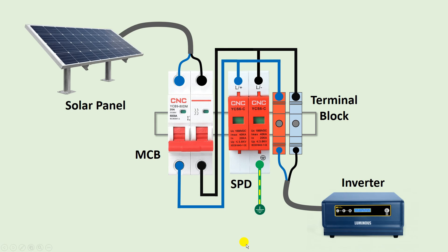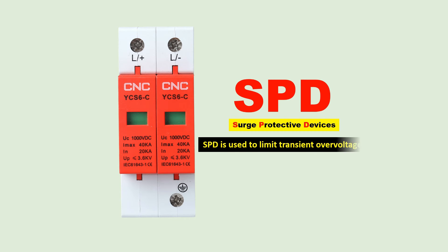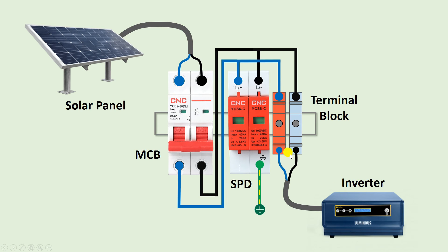Now let us understand why we should use a DC DB. As you know, sometimes suddenly voltage goes high in our homes. If voltage increases rapidly, electrical devices can become faulty. If you want to protect them, you have to use an SPD. In simple words, if the voltage suddenly increases too much, the SPD reduces it — it provides only the voltage required for the inverter. This is why the power supply from the solar panel is connected first with the MCB and then with the SPD. The MCB gives protection from overcurrent and short circuit, and the SPD provides protection from surge voltage.